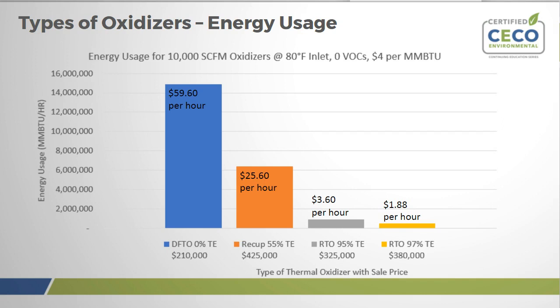This is directly a result of the heat recovery capabilities of each of the oxidizers. So the RTO on the far right is the best. But this also plays into the applicability for a given process. Oxidizers that require a large amount of heat to stay up to temperature would be a DFTO or a recuperative on the left, because they release a lot of heat, so they require a lot of heat input.